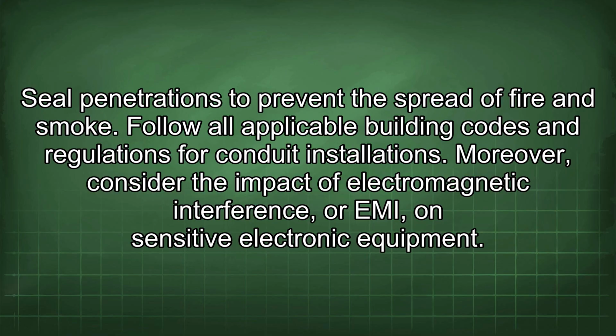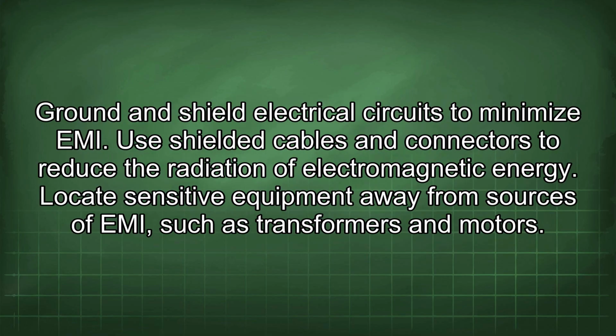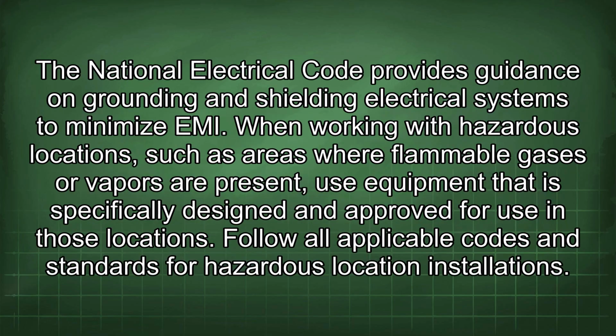Moreover, consider the impact of electromagnetic interference, or EMI, on sensitive electronic equipment. Ground and shield electrical circuits to minimize EMI. Use shielded cables and connectors to reduce the radiation of electromagnetic energy. Locate sensitive equipment away from sources of EMI, such as transformers and motors. The National Electrical Code provides guidance on grounding and shielding electrical systems to minimize EMI.